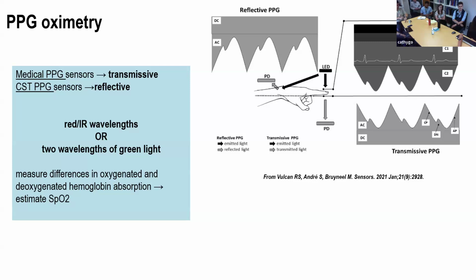Something to keep in mind is that medical PPG sensors, so medical grade pulse oximeters, are transmissive. That means the photoplethysmography light source, the LED, is across the vascular bed from the photodetector, or I should say the opposite: the photodetector is across the vascular bed from the LED light source. So you have the vascular bed between these. You're going to get a much more secure fit. With a smartwatch that uses photoplethysmography, the photodetector is in the same plane as the LED. It's reflective photoplethysmography, and you've seen how people, especially me, wear their watch. So you obviously don't have as secure a fit. That is going to be a source of artifact.